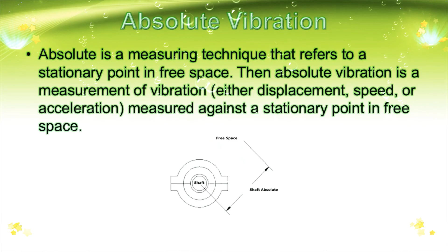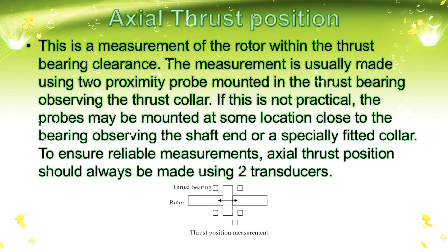Now it is about axial thrust position. This is the measurement of the rotor with the thrust bearing clearance. The measurement is usually made using two proximity probes mounted in the thrust bearing observing the thrust collar. If this is not practical, the probe may be mounted at some location close to the bearing, observing the shaft end, or a specially fitted collar to ensure reliable measurement. Axial thrust position should always be made using two transducers.